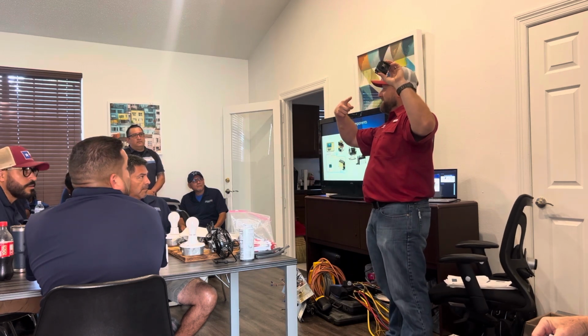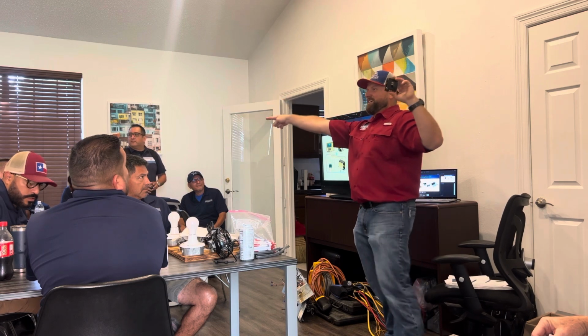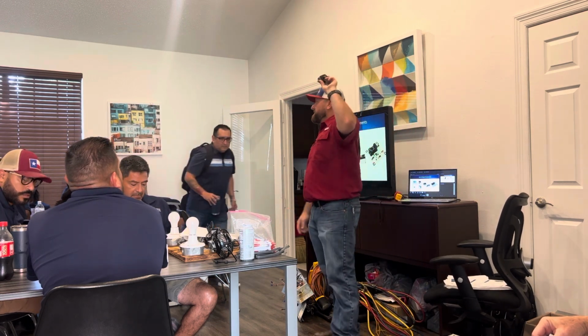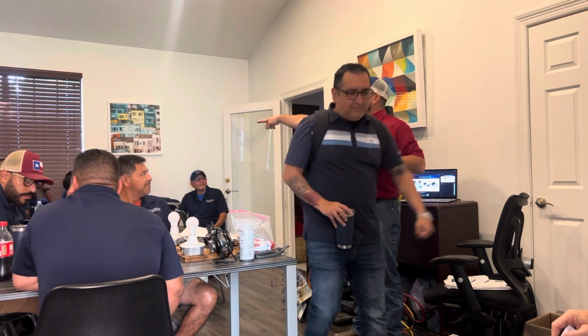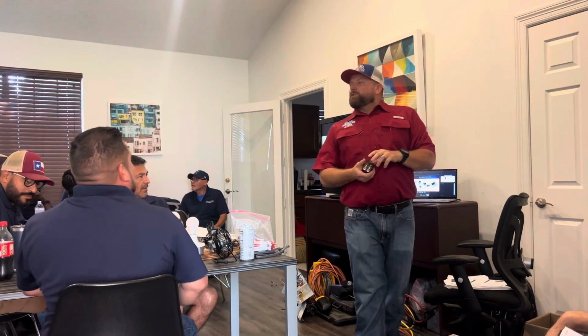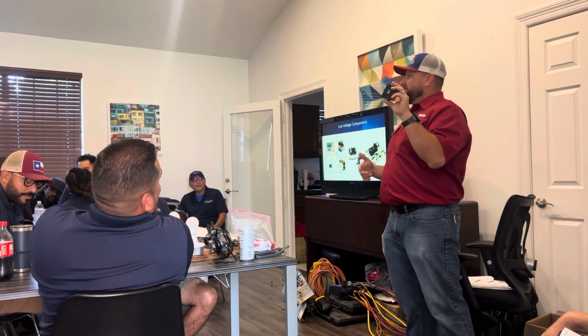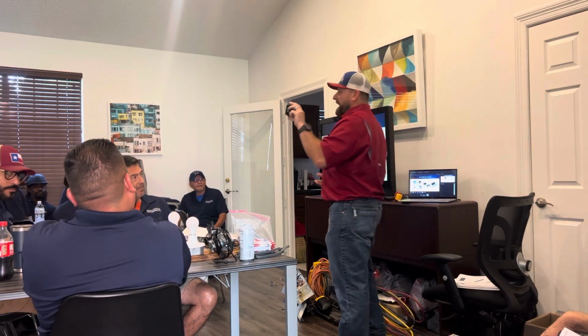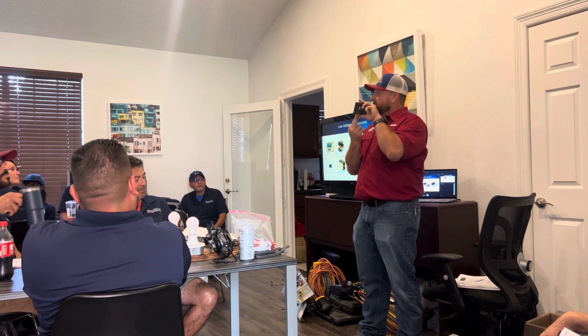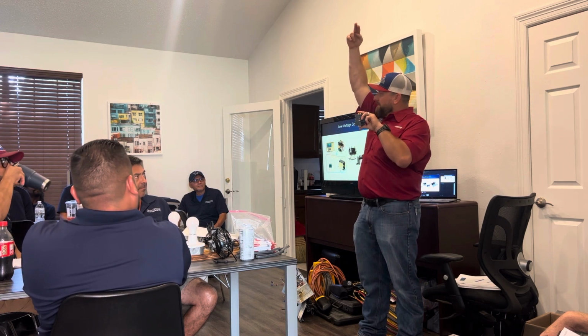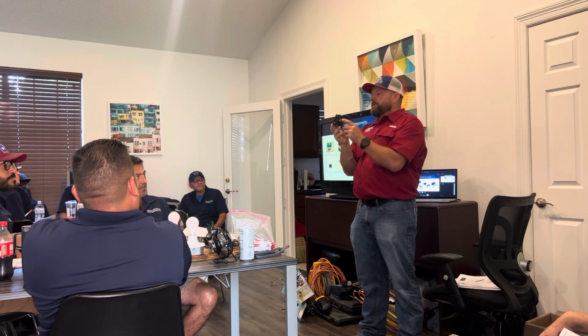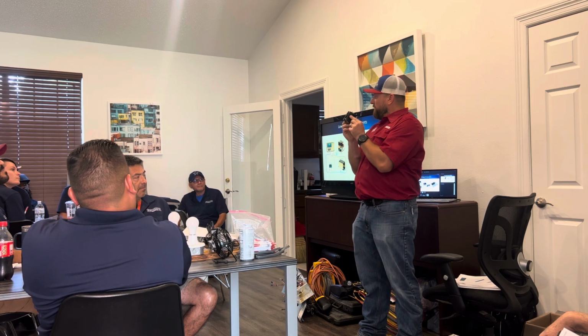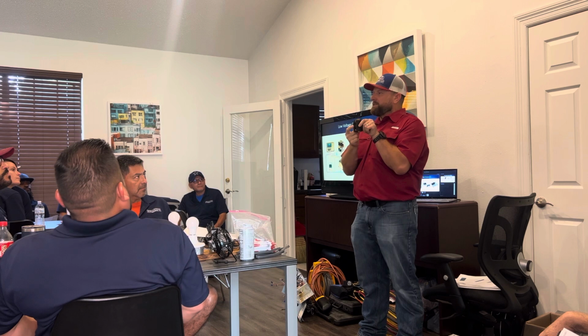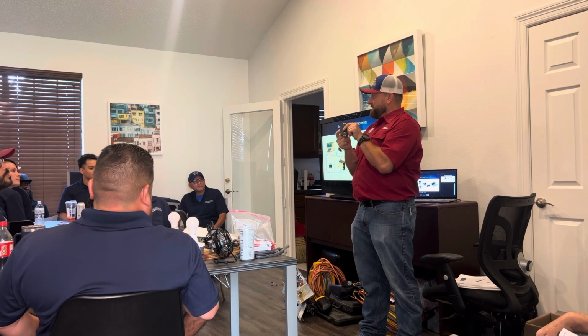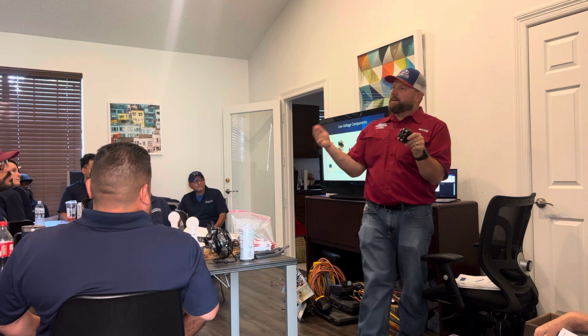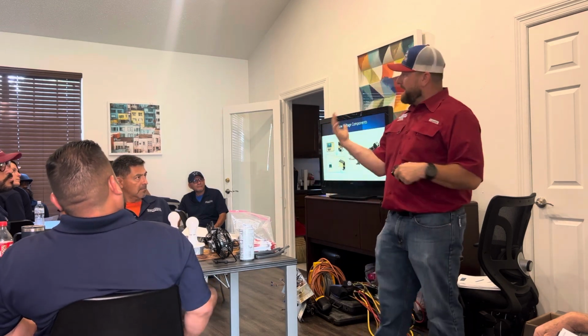That's right, it's a contactor, right here in the hat. So what this contactor does, just as a refresher: high voltage comes in here from the disconnect, and then high voltage comes out. Whenever we get 24 volts on this side of it, when it calls for it, it sucks in this contactor. Does that make sense? Does that kind of solidify that low voltage brings in high voltage?